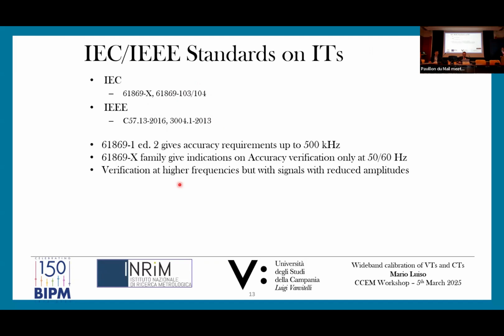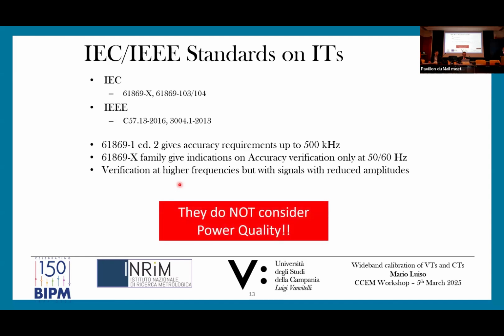The recent standard 61869-1 edition 2 gives accuracy requirements up to 500 kilohertz, but only requirements without giving indication on how to test these instrument transformers up to so high frequency. In general, the standard family gives indication on accuracy verification only at 50-60 Hertz, and says to verify at higher frequency, but with signals with reduced amplitudes. So, summarizing, they do not consider power quality.